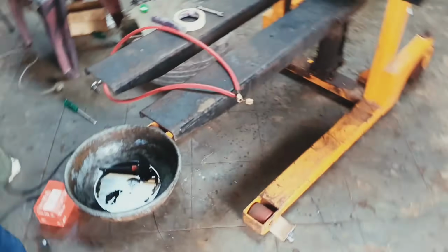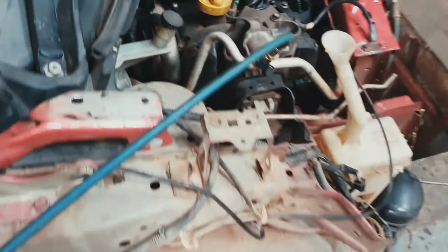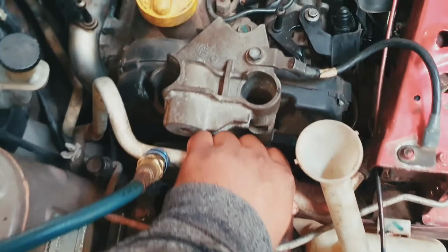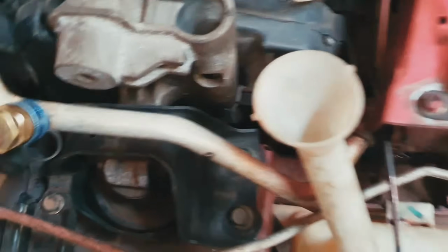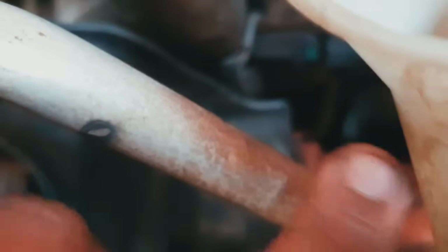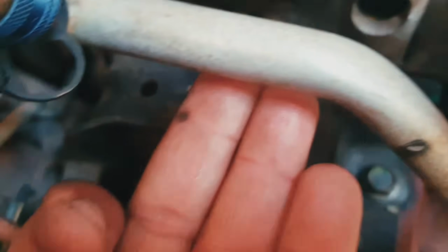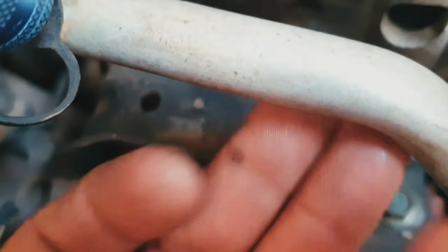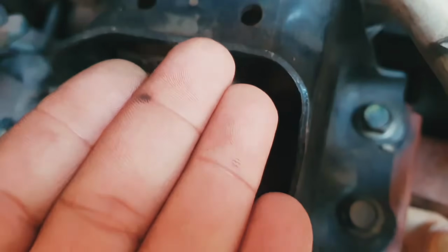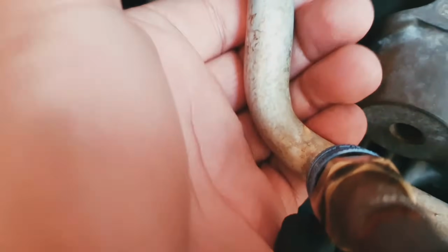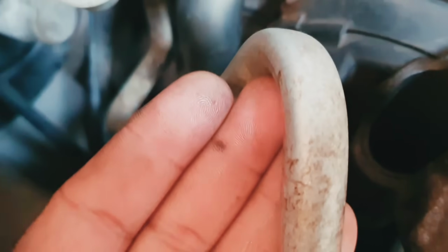You will know it is operating very nicely when you touch this pipe and it is ice cold. Right now it is ice cold, and you can see a little bit of moisture droplets here. I hope you can see them, little small moisture like water. Let me dry my hand here. You can see my hand is dry now, but I'll touch this pipe and you can see now it's wet.